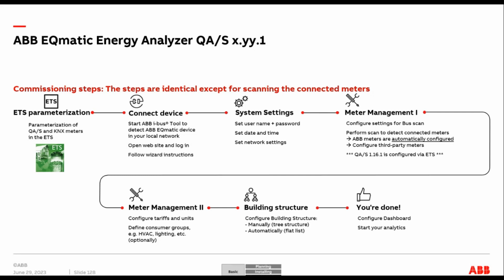Next we'll do our meter management and configure settings for bus scans if needed. You'll see I've starred the bottom section for the KNX version of this device — all these settings are done in ETS, which I'll show you because it's important to get right.